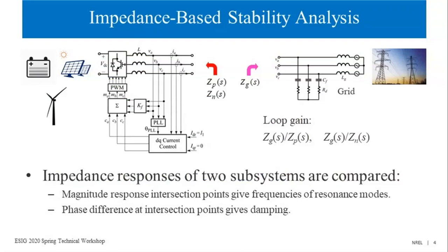Impedance-based stability analysis has become more attractive recently, mainly because it doesn't require internal details of controls of inverter-based resources and just uses impedance responses. In this slide, I show a very simplified representation of the impedance approach, where we compare the impedance of two interacting subsystems like a wind power plant and the grid. But there are many variations of this. The impedance can be sequence impedances, DQ impedances, phasor impedances, and many other variations.